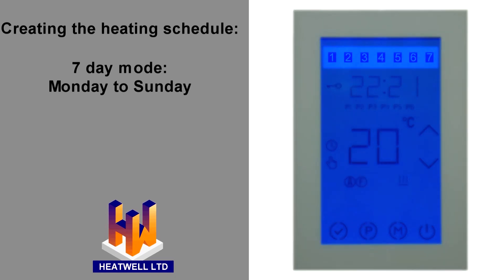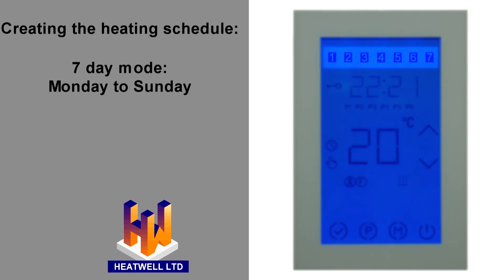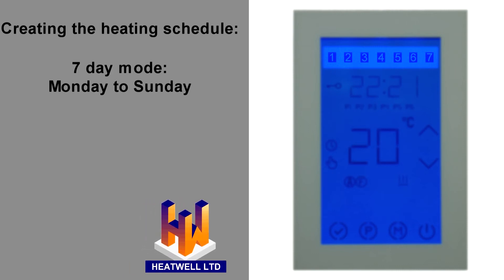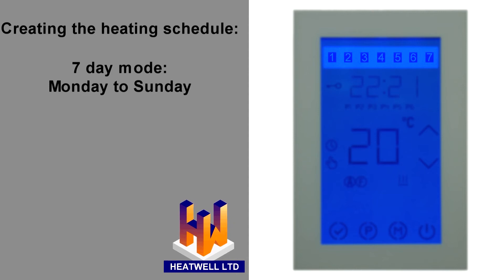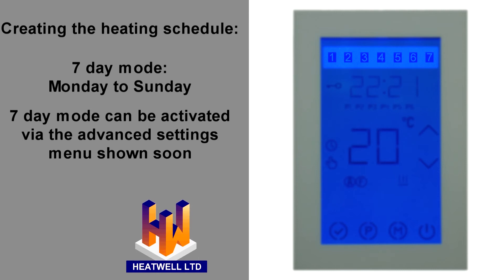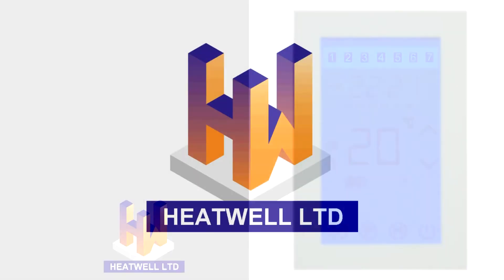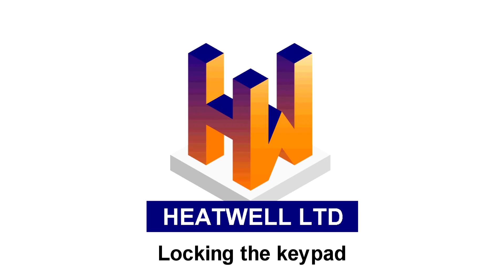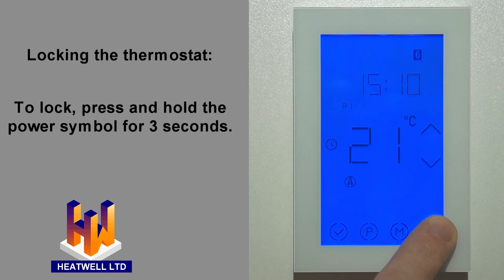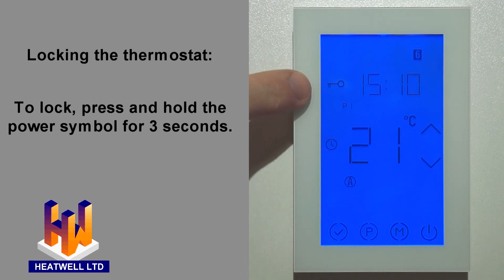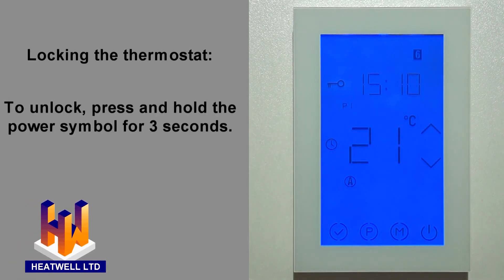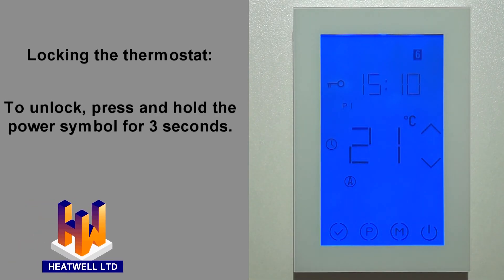7-day mode is programmed in the exact same way, with Saturday and Sunday appearing along with the weekdays. This is because 7-day mode uses the same temperatures and switch-on times all day, every day. 7-day mode is not active by default, but can be activated in the advanced settings shown shortly in the video. To lock the keypad, press and hold the power button for 3 seconds. The key symbol will appear, which means the thermostat is locked and unable to be changed. To unlock the unit, press the power button again for 3 seconds.